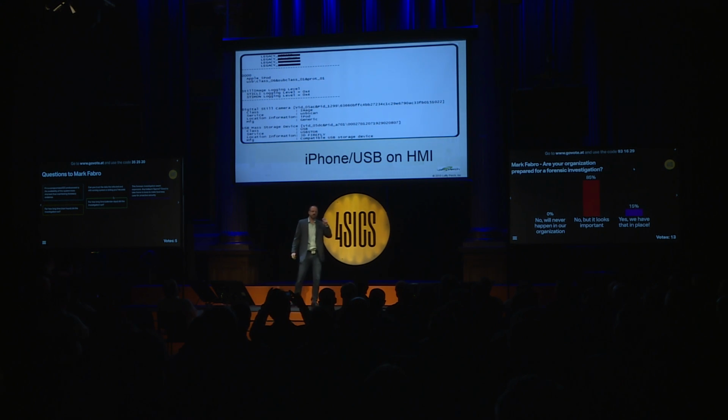It then occurred to us, wait a second. Is there a possibility that someone used this for personal gain during the build process? We're looking in the wrong spot. There should be evidence that maybe someone didn't do it intentionally, but something came in somehow through some other networking component, got onto a device that was inserted into it, never scanned, and actually went out as the HMI. We began to parse through files you would never look at when you're doing incident response on something like a control system.